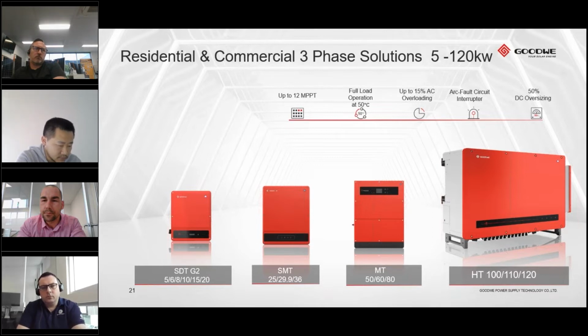Another unique feature about the SMT series is that it has 1100 volts as a DC input voltage, and this effectively means that you can put an extra 2 panels in each of your strings. So just adding greater flexibility for the installer. And on top of that, another really unique feature is the DC cover. So we have a DC cover that comes as standard, and that covers the DC inputs and also the DC isolator. And basically that alleviates the need for the installer to put a cage or a barrier around the inverter because we've put that there for them.